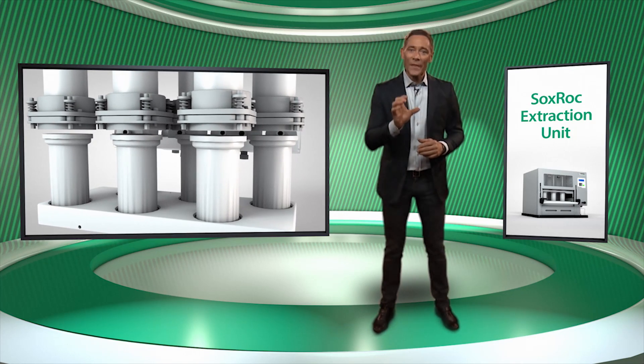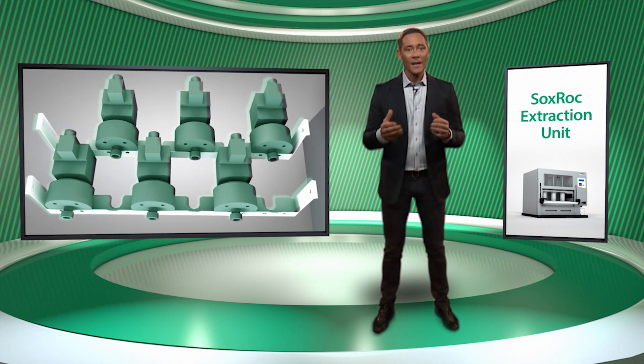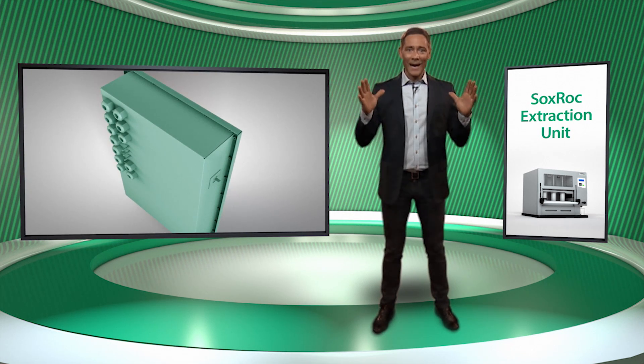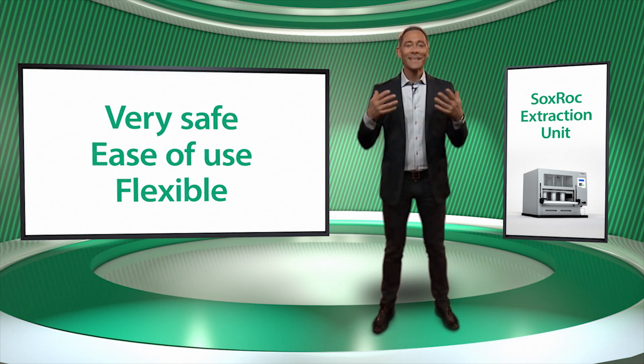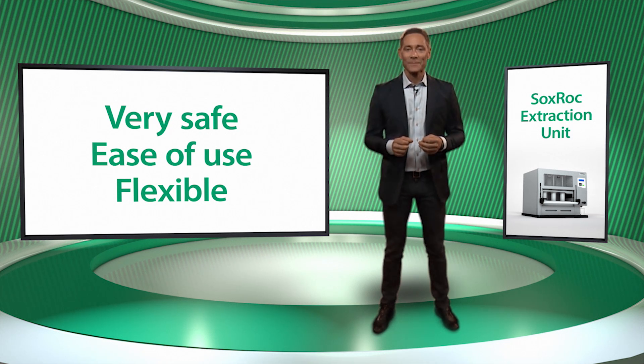As we have seen, the SoxRoc is solidly constructed and very safe, as well as flexible and easy to use. It is sealed — more than 90% of the solvent remains in the instrument. The valves are EX classified and the main electronics are housed in a pressurized box. It is easy to use with a unique rack and user-friendly interface, and it is flexible across a large range of applications.